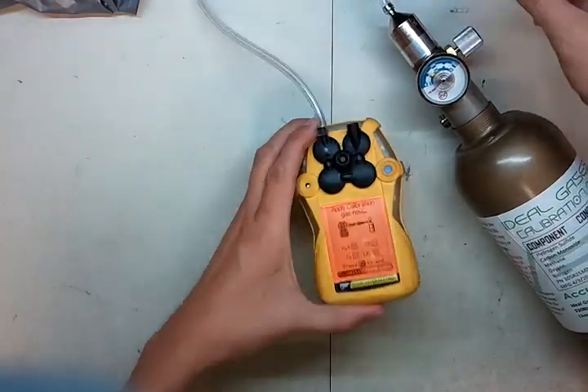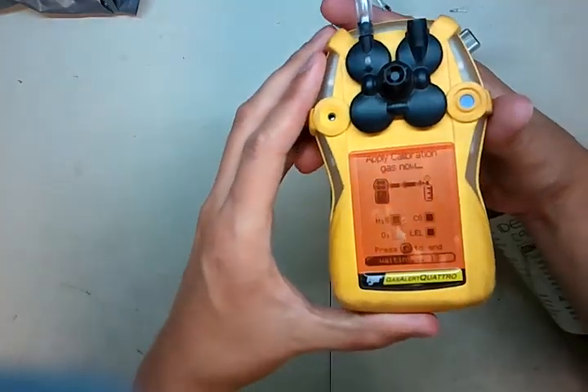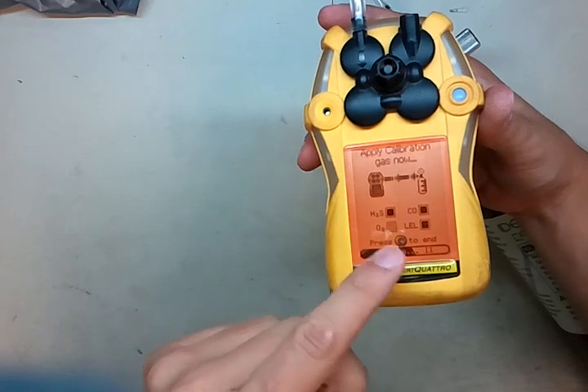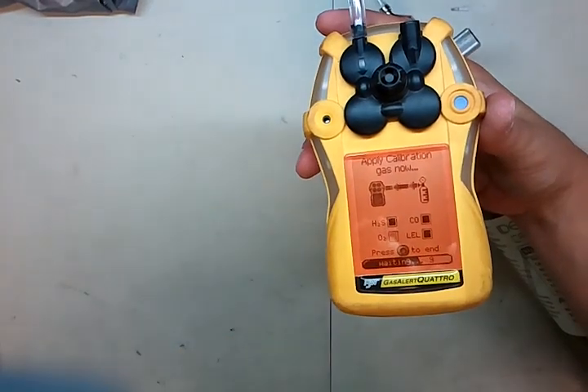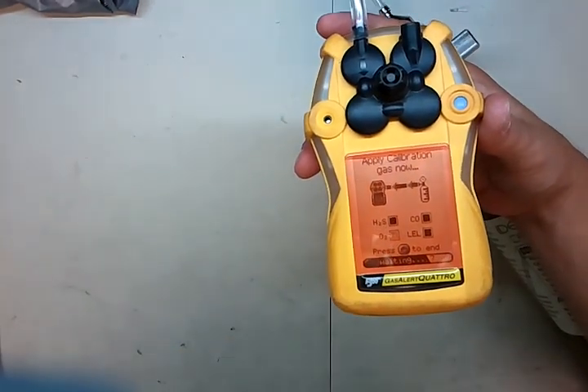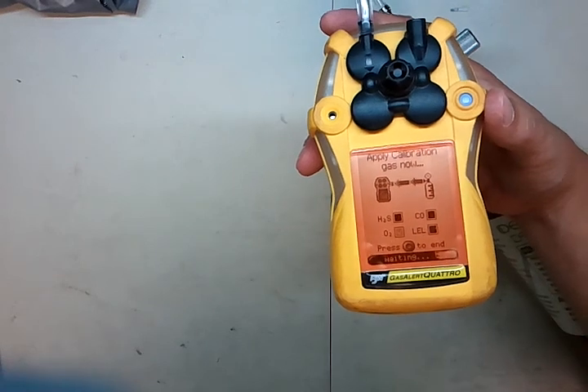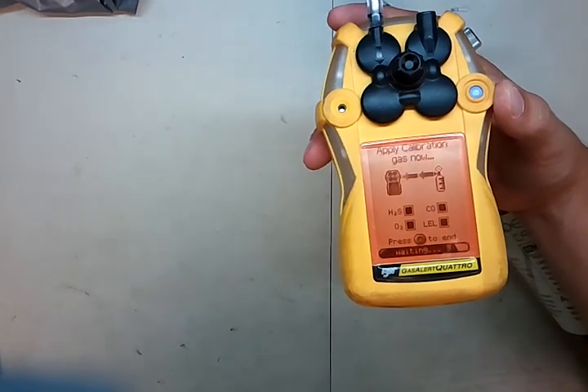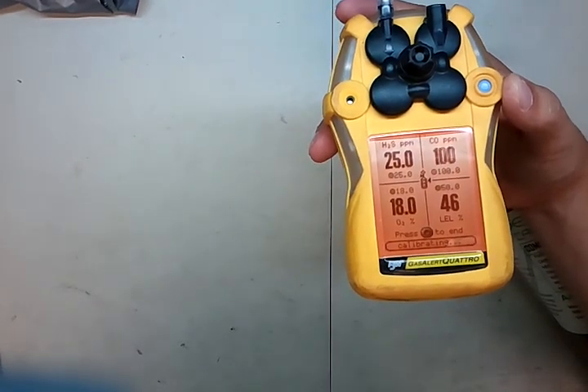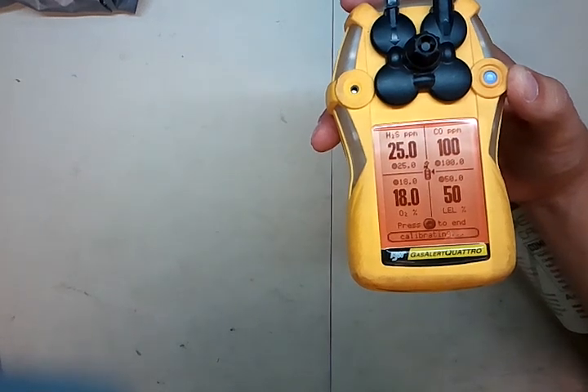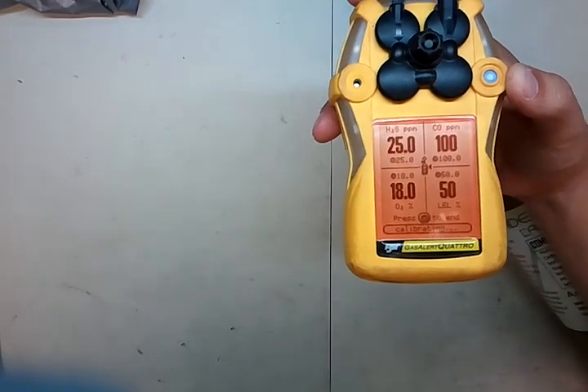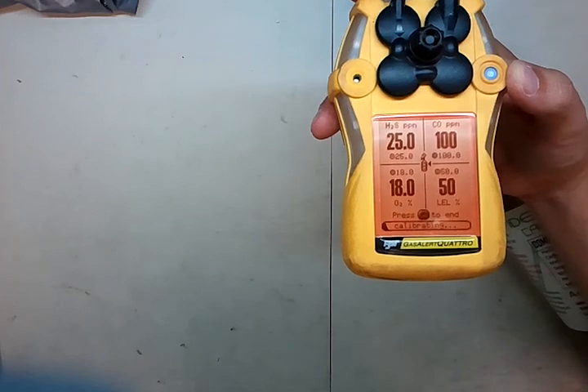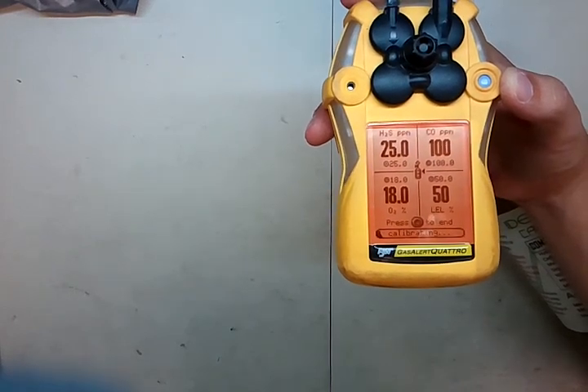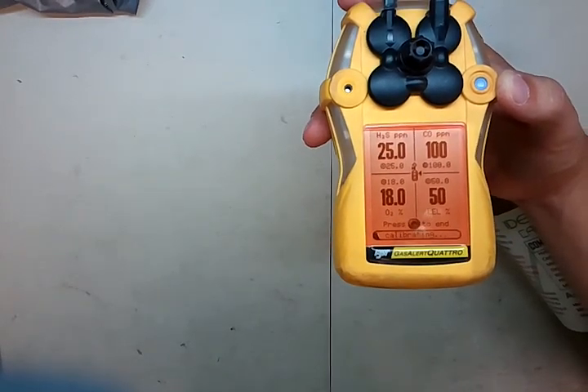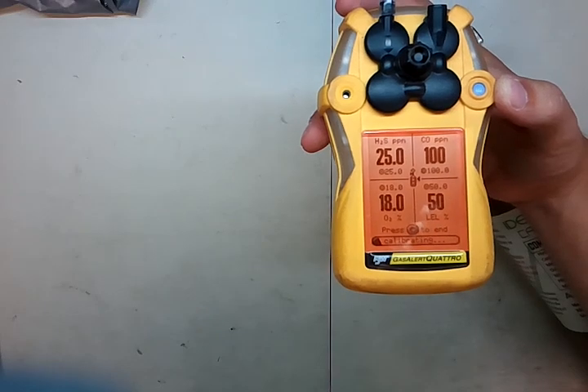One of the cool things is as it's going, see how the boxes light up dark? It tells you it's detected that the gas is there, and it's going to calibrate to those. Oxygen seems to take the longest. There we go. Now it comes up with the gas values. These detect pretty quick, so this one should be a fairly quick calibration for us compared to some of the other monitors. I know a number of them out there take a lot longer than this.